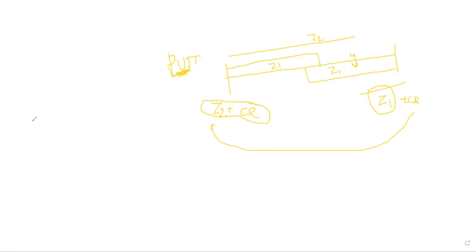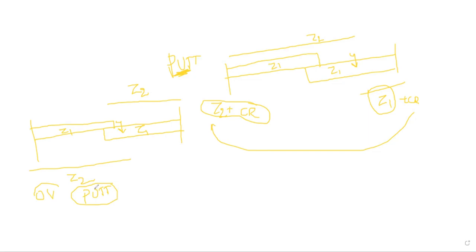Okay, now overreach. Zone 1. Now a fault occurred here. Zone 2. Maybe due to the fault arc resistance, this end is also showing zone 2. Got my point? So zone 2, overreach, permissive scheme. Actually, what you are saying first is the overreach. Underreach is when the fault is below 80% of the line, that is underreach actually.